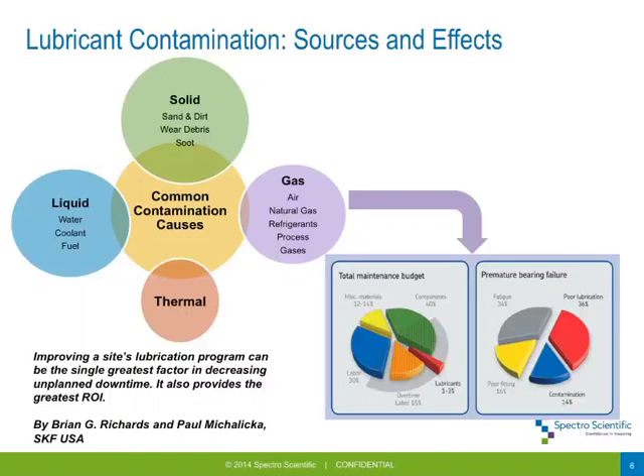We mentioned that the webinar is going to focus on lubricant contamination. What is lubricant contamination? We look at it as a series of potential items that can cause damage and get into the oil. It might be solid contamination — sand and dirt getting into the system — causing wear debris. It could be soot content particles causing abrasive problems. It can also be liquid contamination: water, coolant, fuel, or glycol.